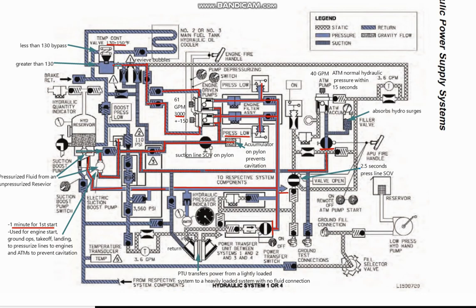Basically, if it's above 130 degrees, it's going to modulate in a way that tries to keep the fluid at 130 to 150. So let's say the fluid was above 150, it's going to shift closed, forcing the fluid to make its way up through here, through our heat exchangers, which are in either number 2 or number 3 main fuel tanks.